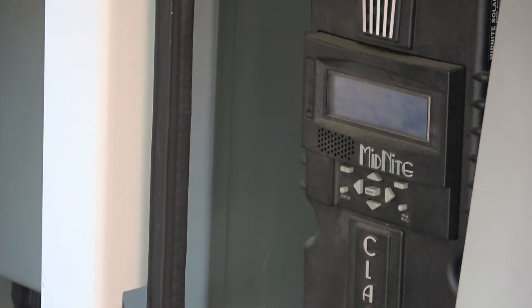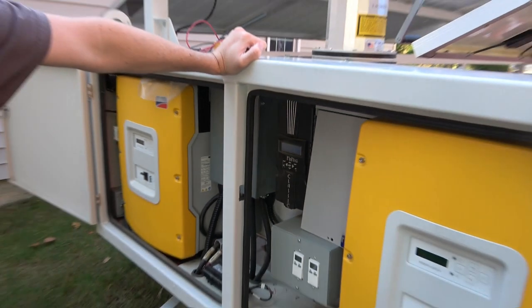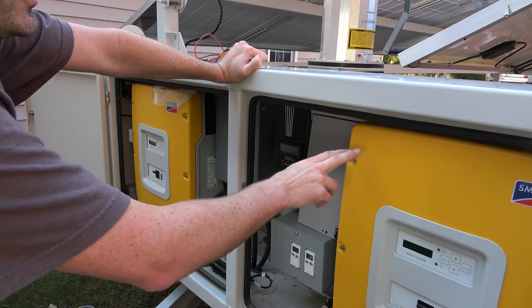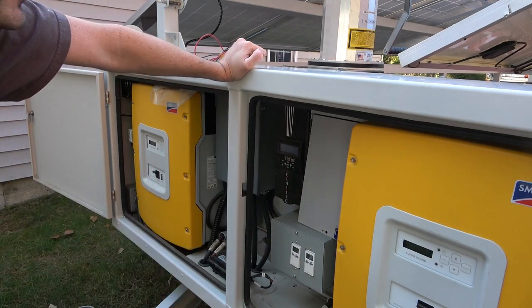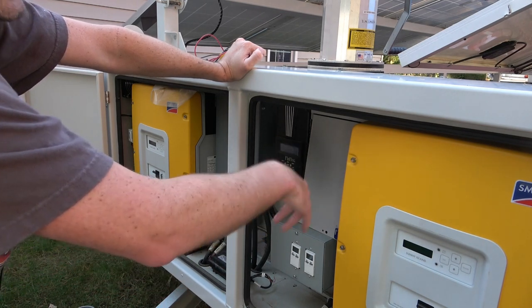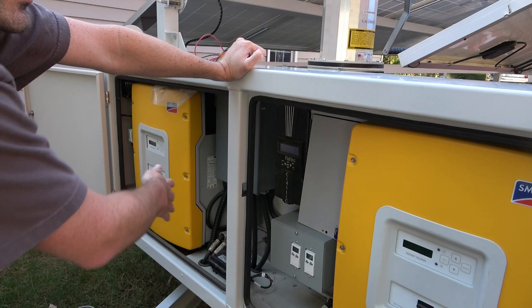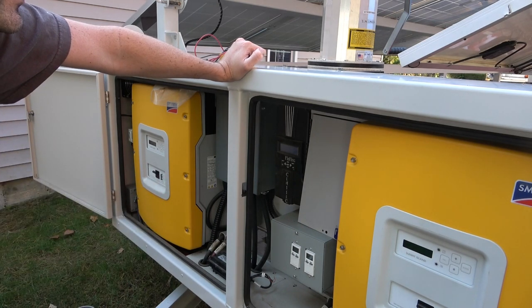So this just basically directs voltage back to the batteries to charge them up, and then these big yellow guys do the inverter. It's a 48 volt system, so although right now it's like 56.5 volts, it'll vary within there, but these guys take that 56 and bump it up to two different legs in order to have 220 or 240 on each trailer.